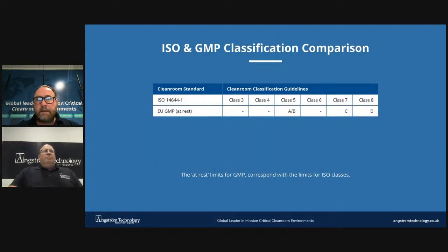This slide just highlights the difference between the ISO and the EU GMP. So the ISO class stays the same for ISO status in operation, at rest and as built, but in GMP, class limits decrease for operational status of the room. For example, grade B reduces from ISO class 5 to class 7, grade C reduces from ISO class 7 to class 8, and grade D reduces from ISO class 8 to unclassified. All reduce with the exception of grade A, which remains the same ISO class 5 in both statuses.